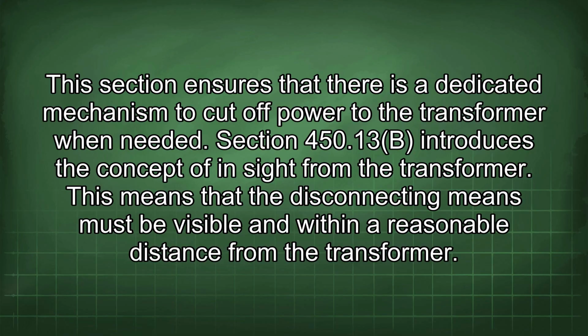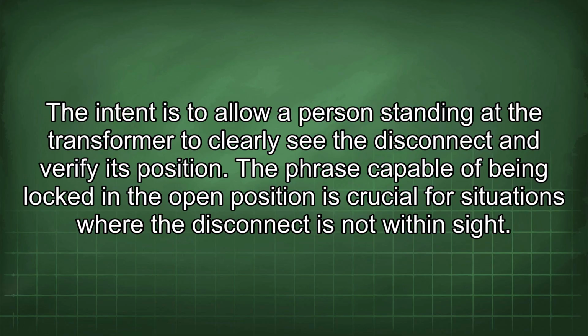Section 450.13(B) introduces the concept of "in sight" from the transformer. This means that the disconnecting means must be visible and within a reasonable distance from the transformer. The intent is to allow a person standing at the transformer to clearly see the disconnect and verify its position.